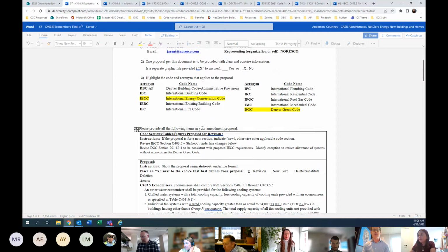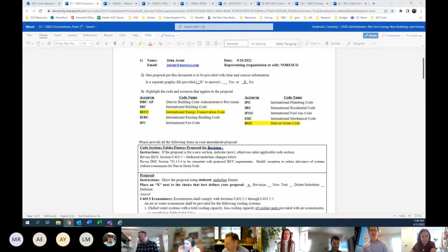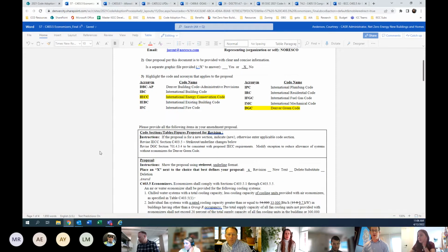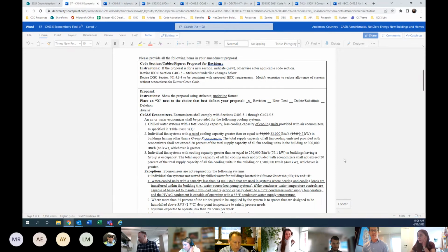The first proposal, this one's fairly straightforward, is to basically expand the scope of where airside economizers are required for HVAC systems. So the proposal here is to expand the requirement for economizers from the current minimum threshold, which is 54,000 BTUs per hour or 4.5 tons, down to 33,000, which is just under 3 tons. So this would effectively, for commercial buildings, bring in systems that have rated capacities of 3 and 4 tons into this requirement.